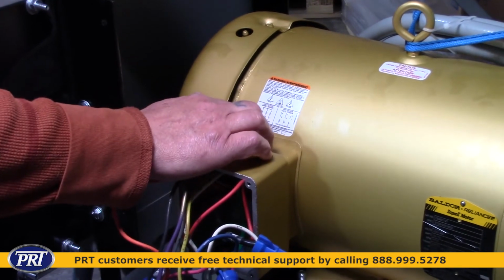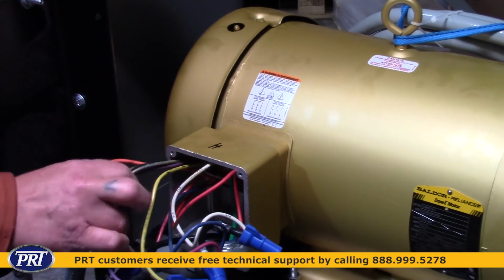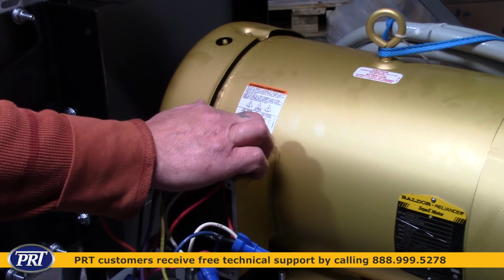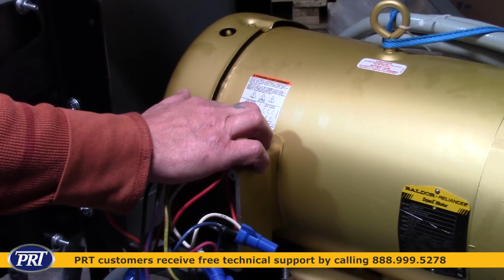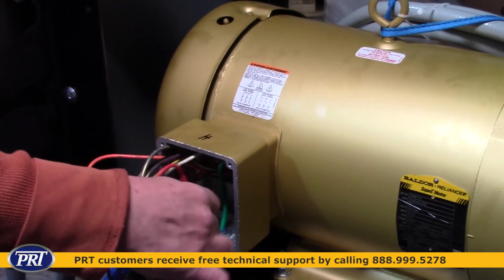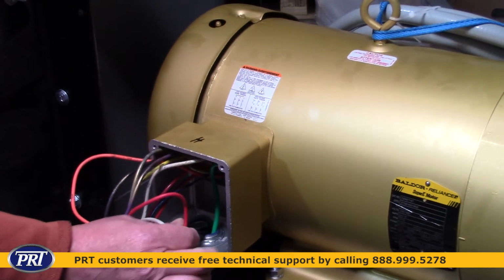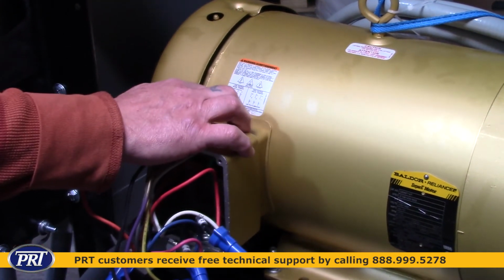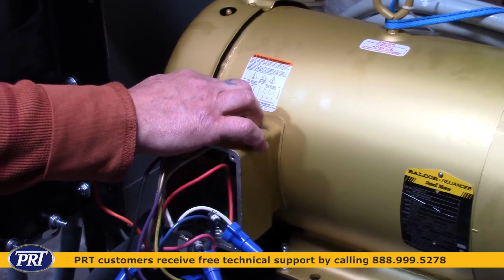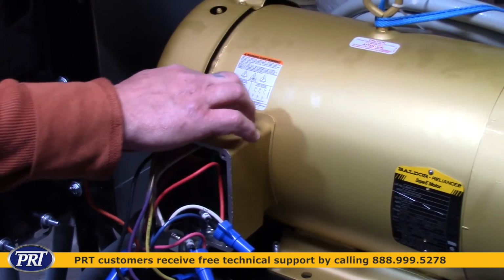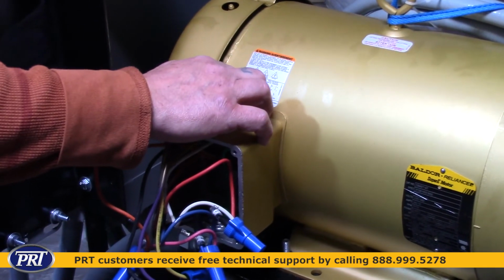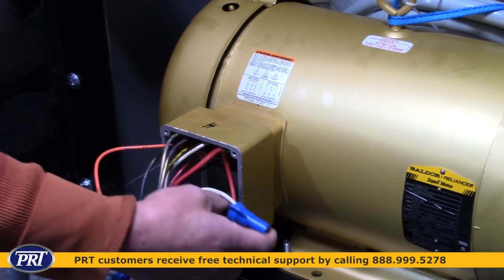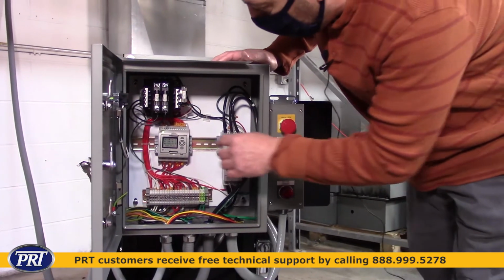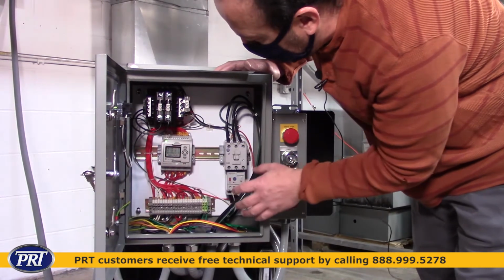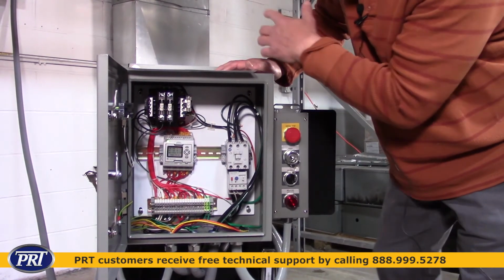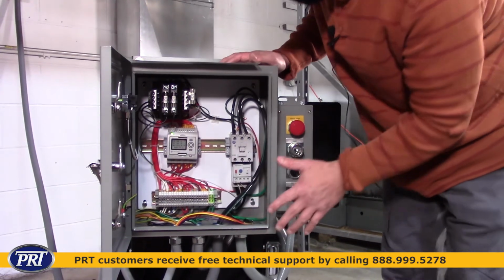The 1 through 9 numbers on here are these little small wires that come with the motor. The 1, 2, and 3 numbers down here on the bottom are actually the motor lines that are coming from your motor starter. And what this is saying is line 3 gets connected with line 9, line 2 and 8, line 1 and 7, and then they're going to go with each line there. Now just make sure when you rewire this, and if you touch anything in here, that the three-phase power is off and there's no electricity in this panel.